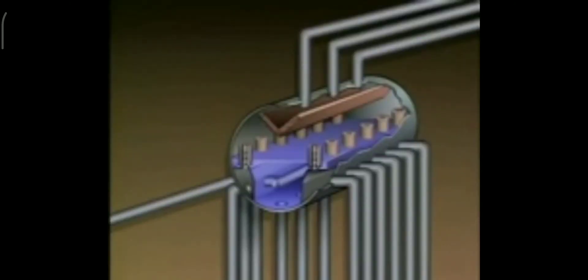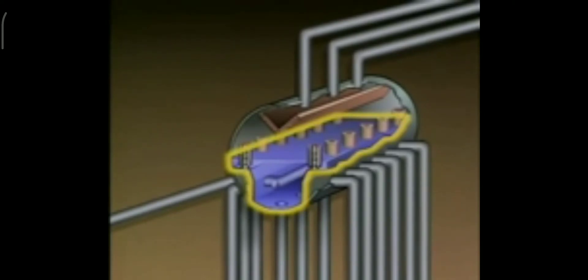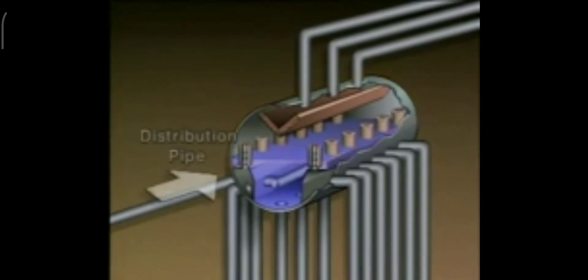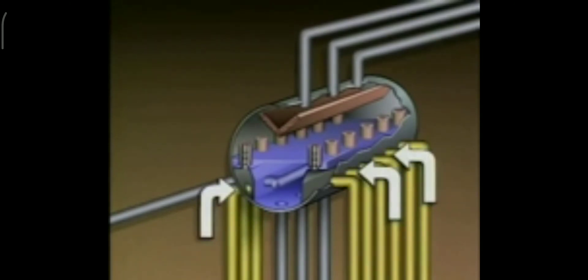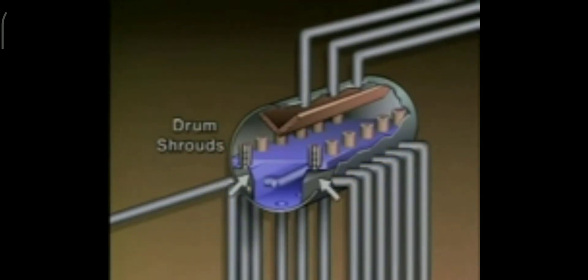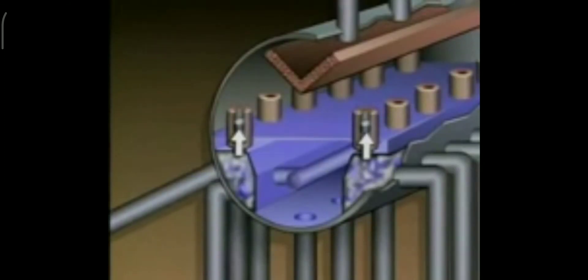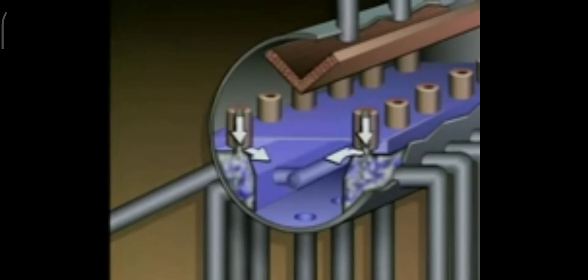A boiler drum has two main functions. The bottom part of the drum contains water to be circulated back through the boiler. The top part of the drum is used to collect steam. Heated feed water is fed into the drum through a distribution pipe. The drum is usually kept about half full of water. The mixture of water and steam that returns to the drum from the water walls is directed against baffles called drum shrouds that run the length of the drum. The shrouds direct the mixture into moisture separators, which are located at the top of the shrouds. The moisture separators separate the water from the steam. The water falls into the lower part of the drum, where it mixes with the feed water.